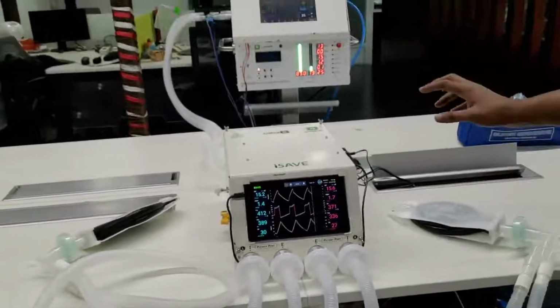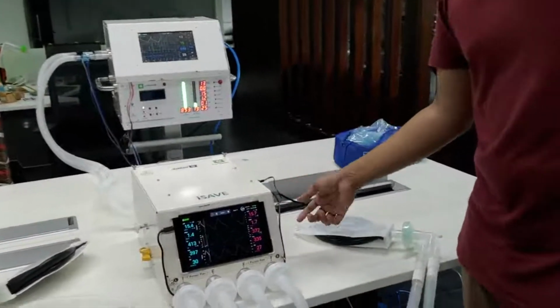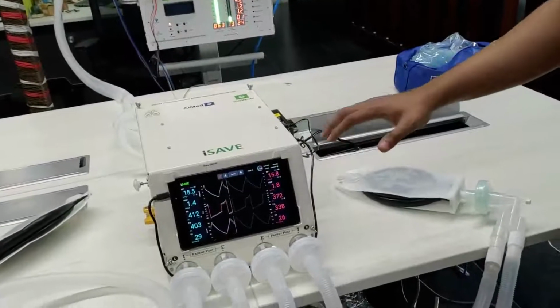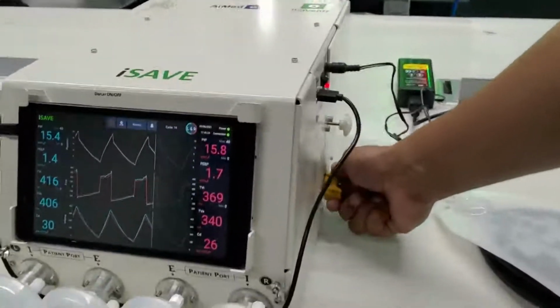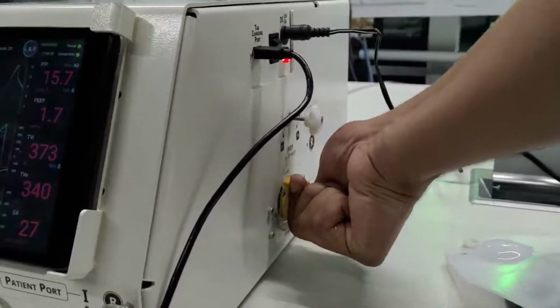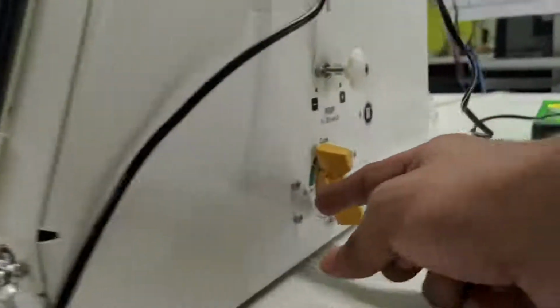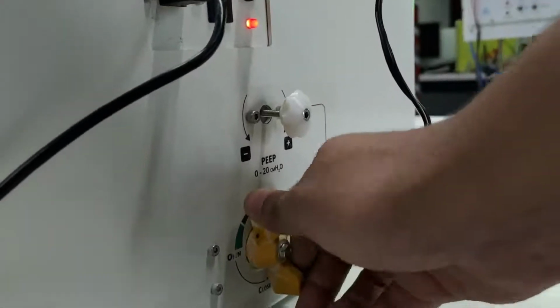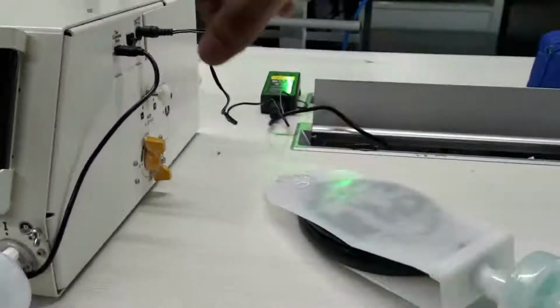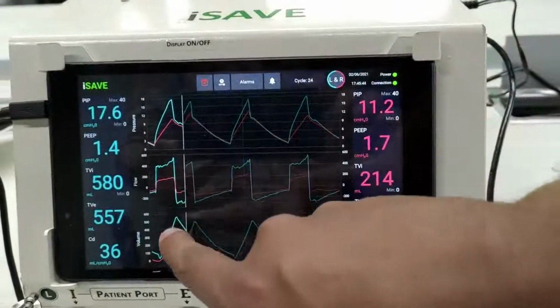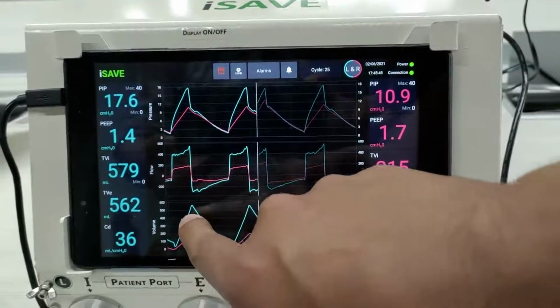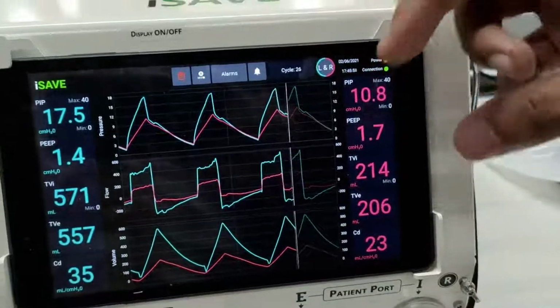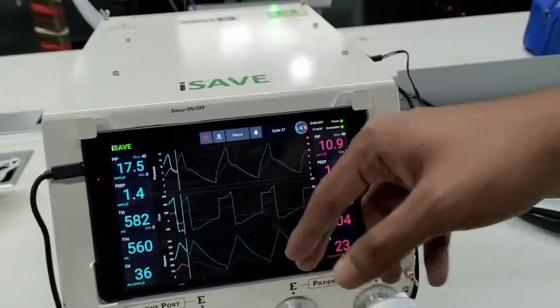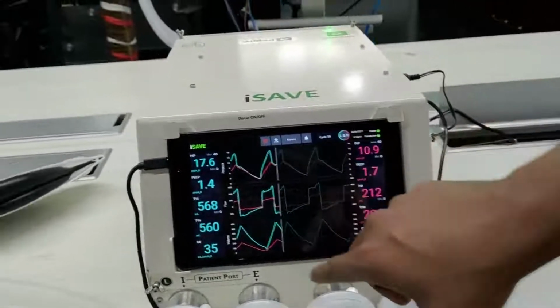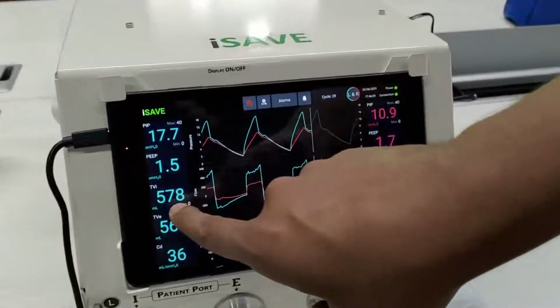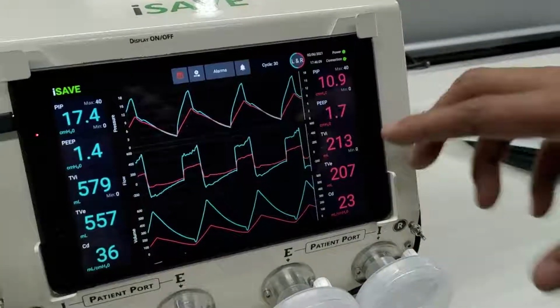Now, a key feature of the iSAVE: we can start to adjust our valves and distribute the flow to the two patients separately. We can turn this valve knob closer to close. Before it was completely open. Now we are reducing what is going into the right patient, and you can see how this is affecting the graphs. The tidal volume for the right patient is much lower than the left patient. We can continually titrate these values to get the appropriate ventilation that we want for each patient from the single ventilator. Here you can see that tidal volume for the left patient is 578. Here it is around 220.